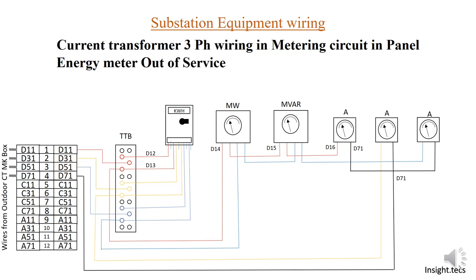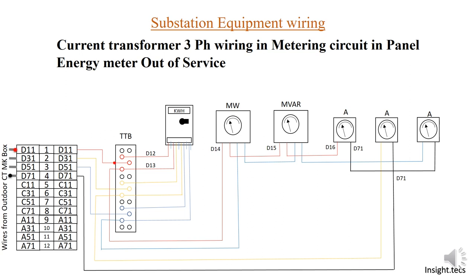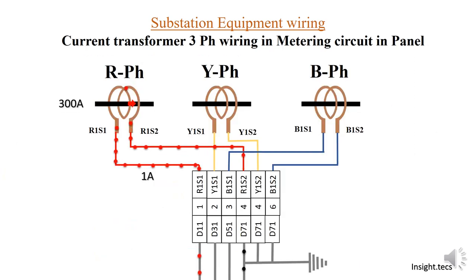If the energy meter is out of service, where will the current go? A small animation will show the alternate path when the energy meter is out of service. As seen in the previous video, this is the R phase current, built in CT at 1 ampere. It goes to D11, passes through all components in the panel, then becomes neutral, and then comes to D71.